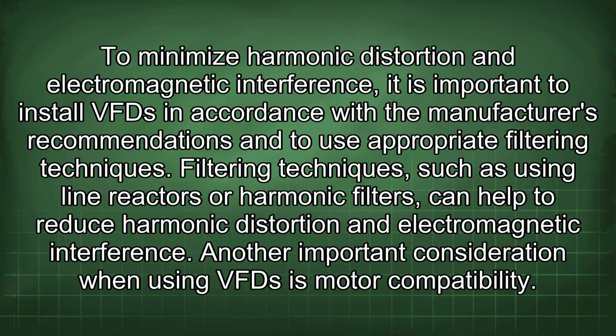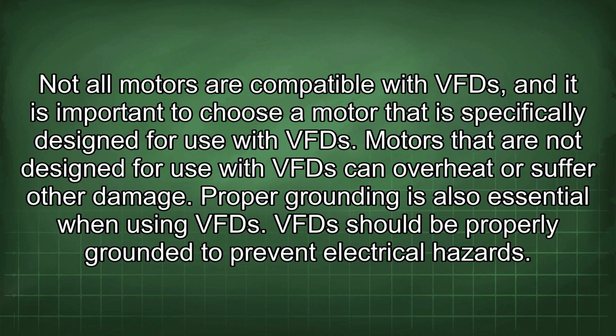Another important consideration when using VFD is motor compatibility. Not all motors are compatible with VFD, and it is important to choose a motor that is specifically designed for use with VFD. Motors that are not designed for use with VFD can overheat or suffer other damage.